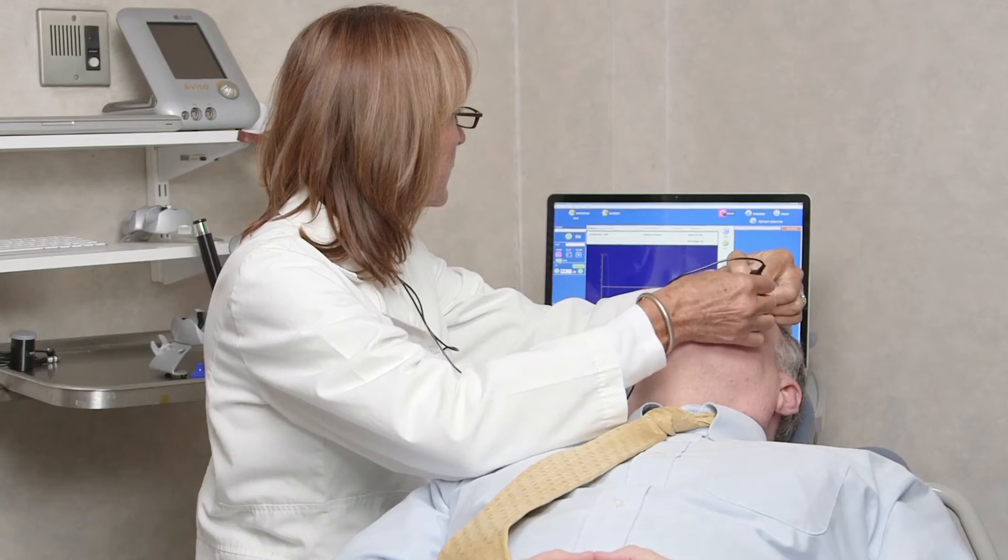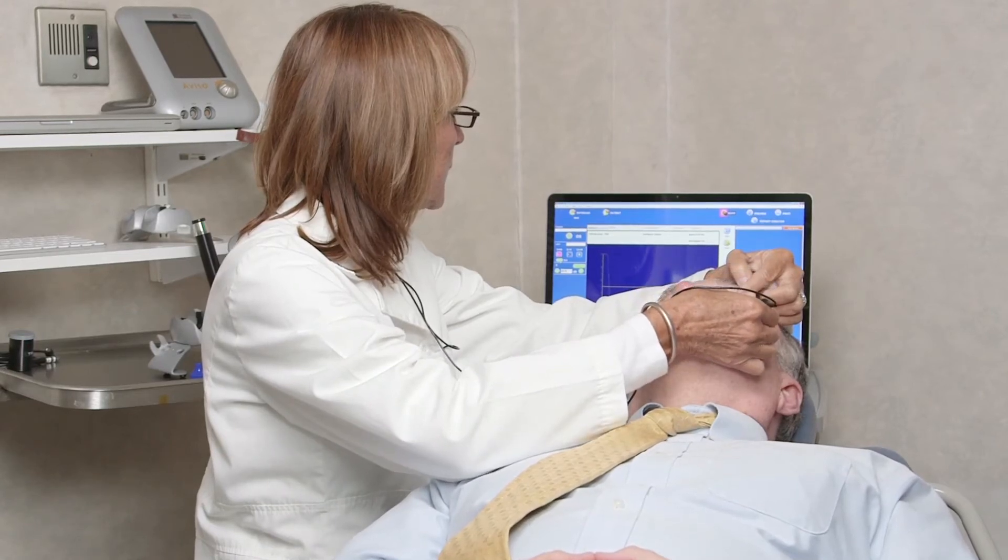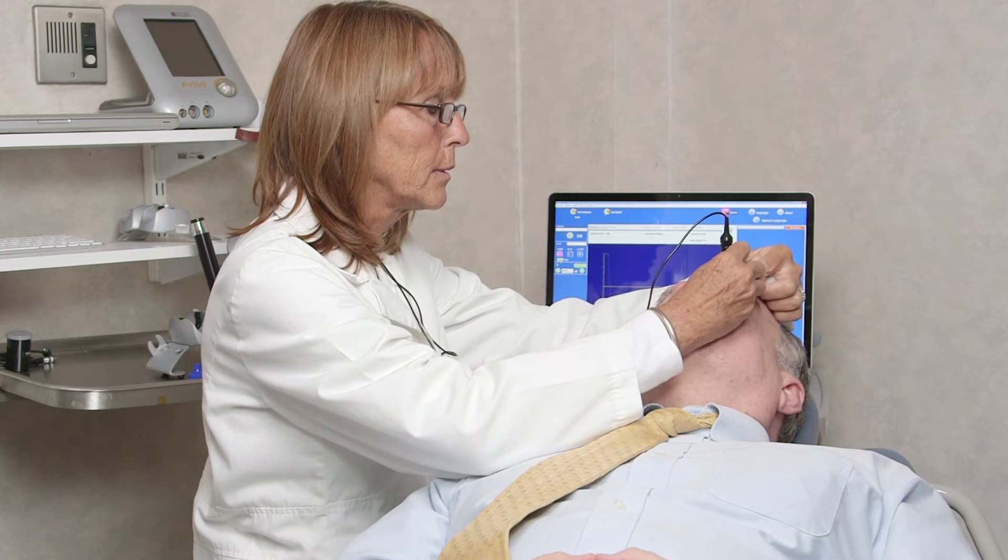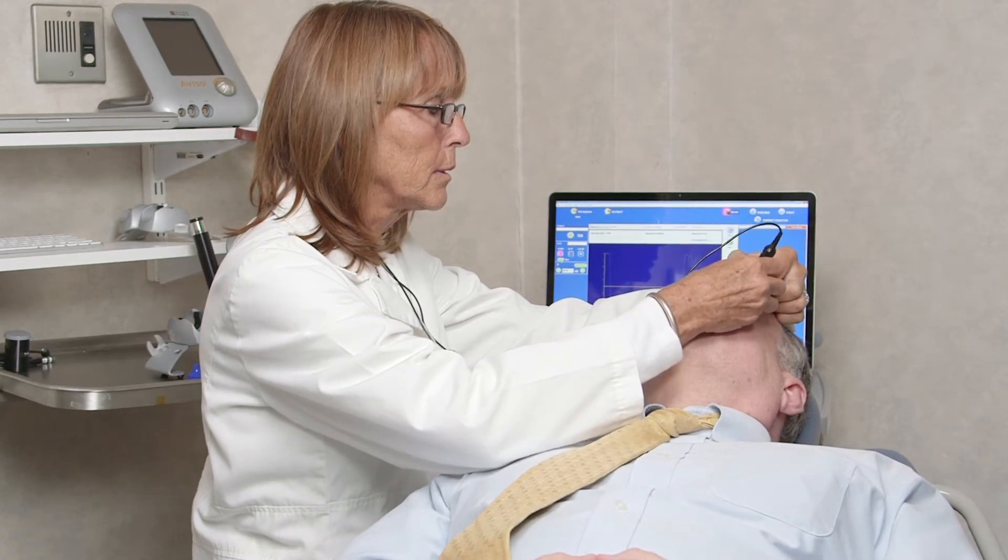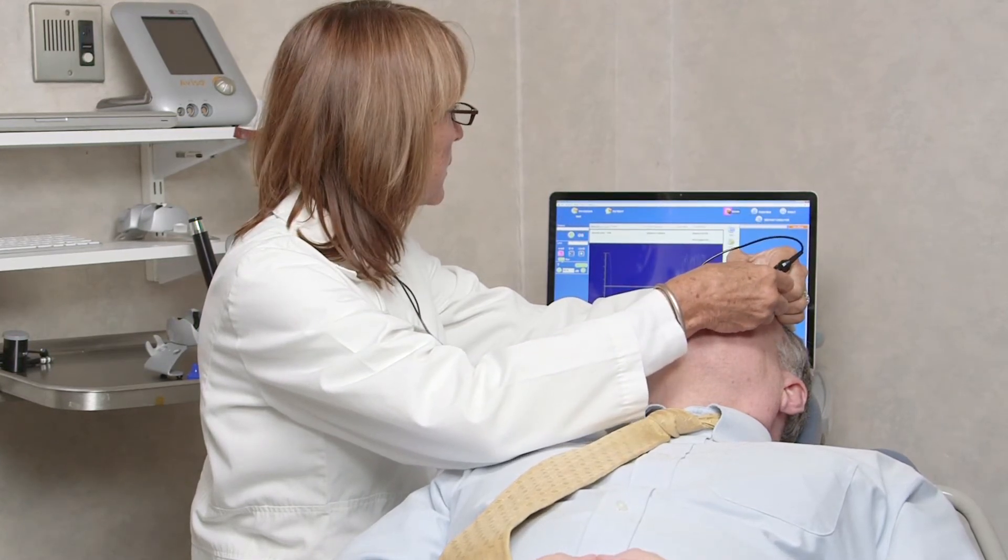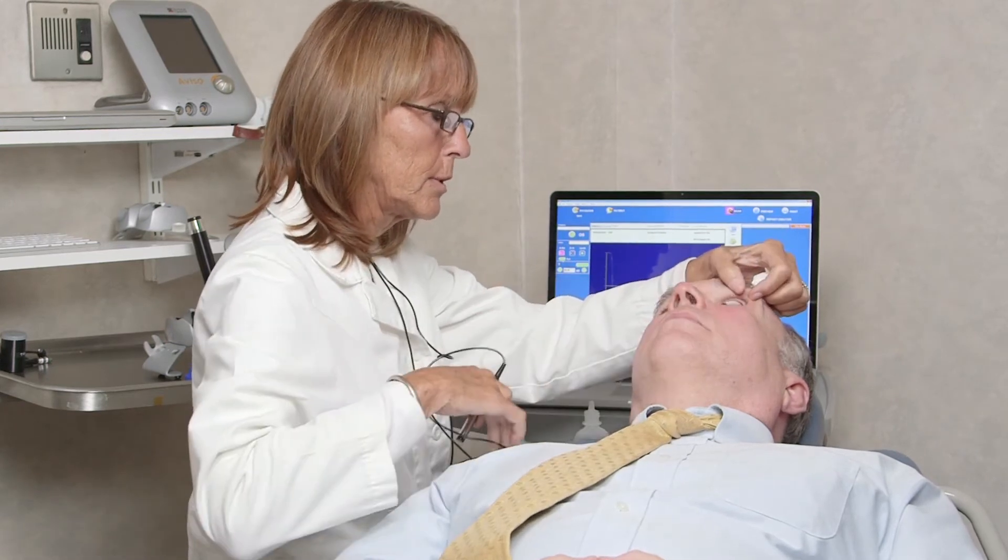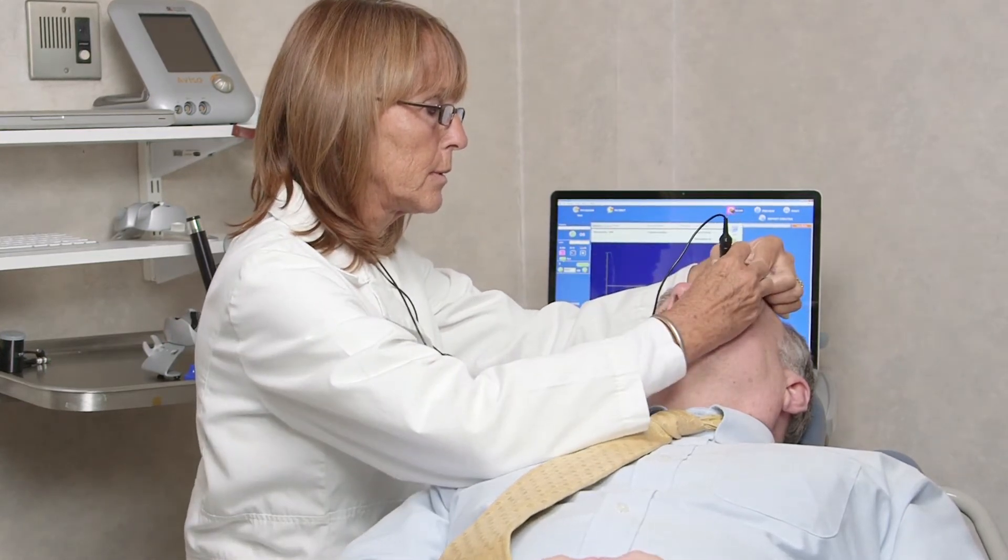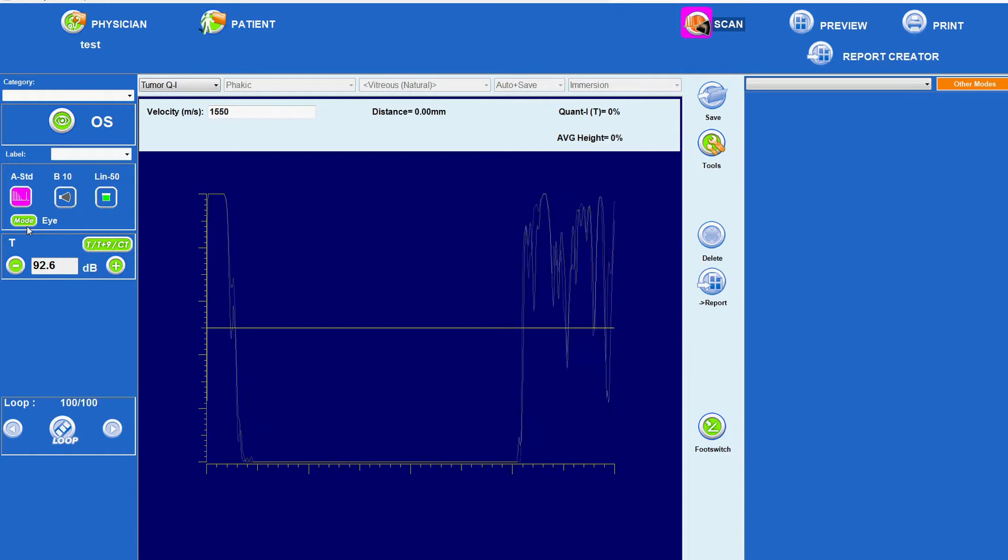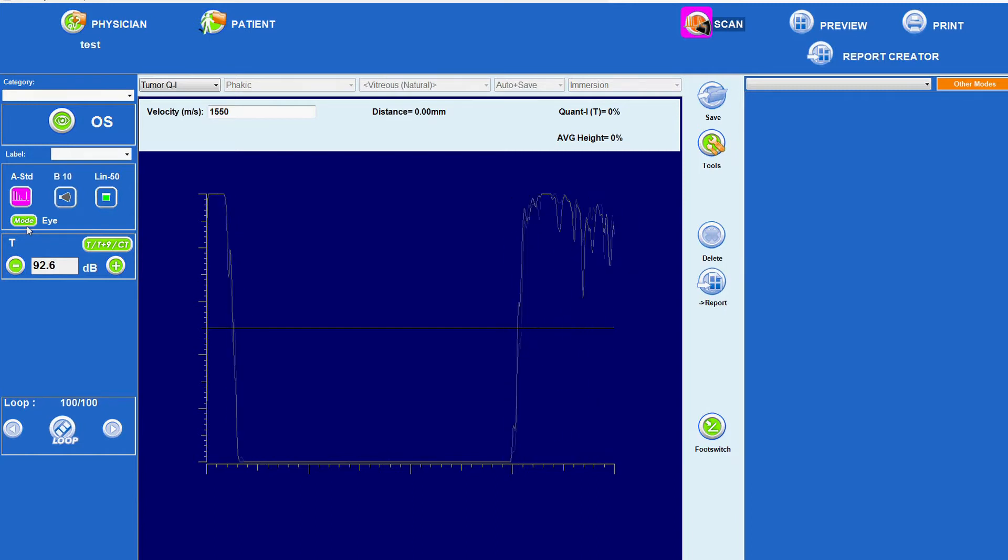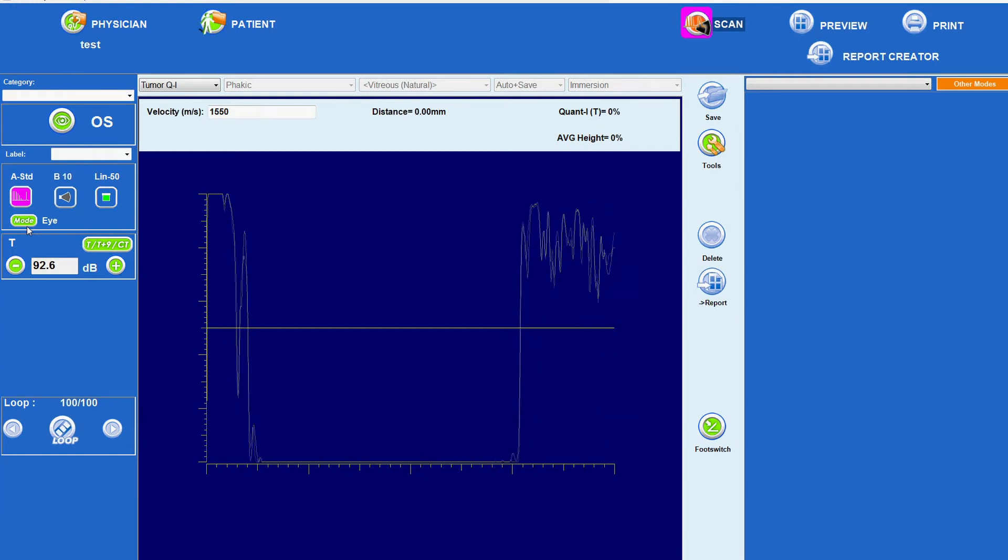Each ultrasound instrument contains an amplifier to boost the signal and enhance the signal-to-noise ratio. When signal intensity in decibels is plotted against signal height in millimeters, the shape of the resulting curve describes the system's sensitivity, its ability to clearly represent different echo intensities as different spike heights, and its dynamic range.